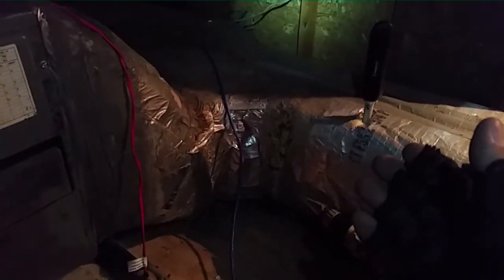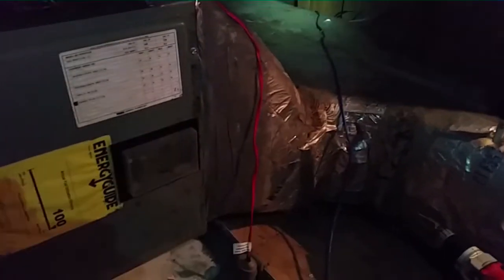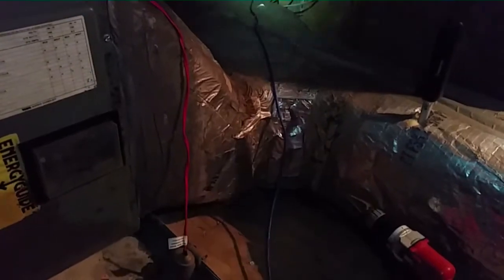As you see the probe I put around the corner here, one of the things that Jim Bergman was mentioning about the probes is the effect of some of our heating and cooling sources like the coil, the heat exchanger, the heat strips, how they have a radiant effect sometimes, and if you put the probe too close to them, it'll affect your temperature split. So I'm trying to take that into consideration by moving it a little bit farther down the stream and out of the line of sight.